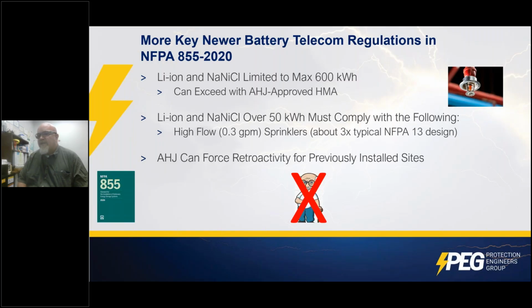Well, with 855, unlike other codes, the AHJ can decide that an existing installation that was installed before 2018 or 2020 or whatever is too dangerous and needs to be fixed before he'll let it operate. Or he may give them some leeway with time to get it fixed and say, hey, I'm going to red tag it if you do not fix these things. We all know that older lithium-ion battery systems are much more liable to go into thermal runaway, so they may require some design changes. Next slide.